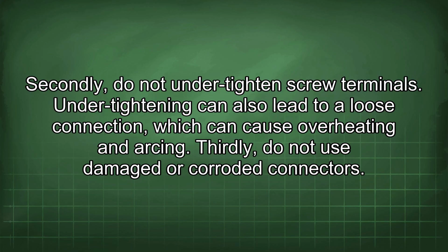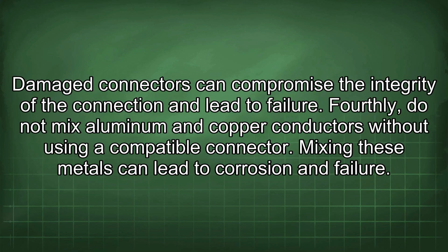Thirdly, do not use damaged or corroded connectors. Damaged connectors can compromise the integrity of the connection and lead to failure. Fourthly, do not mix aluminum and copper conductors without using a compatible connector. Mixing these metals can lead to corrosion and failure.